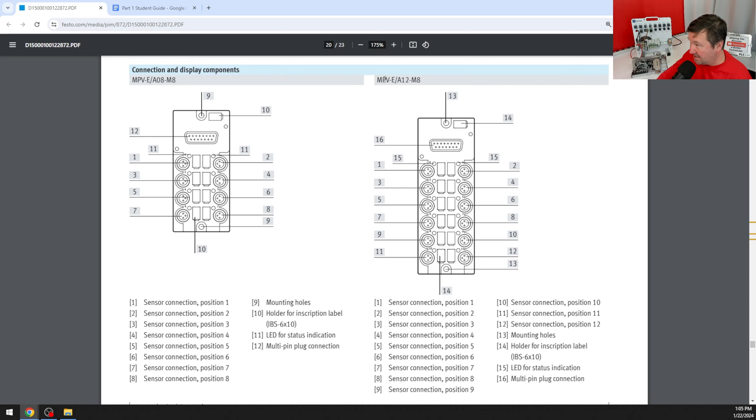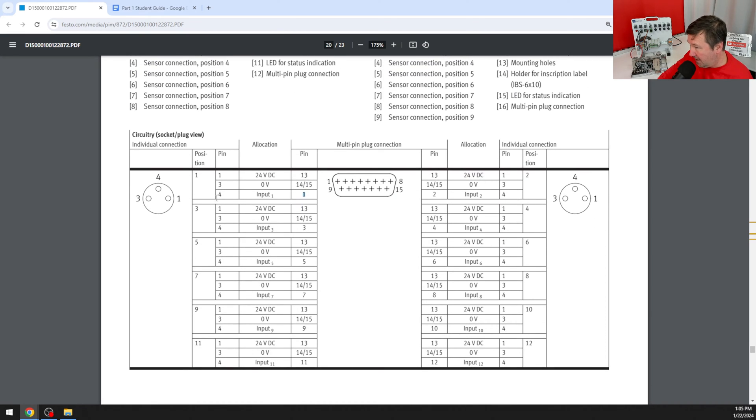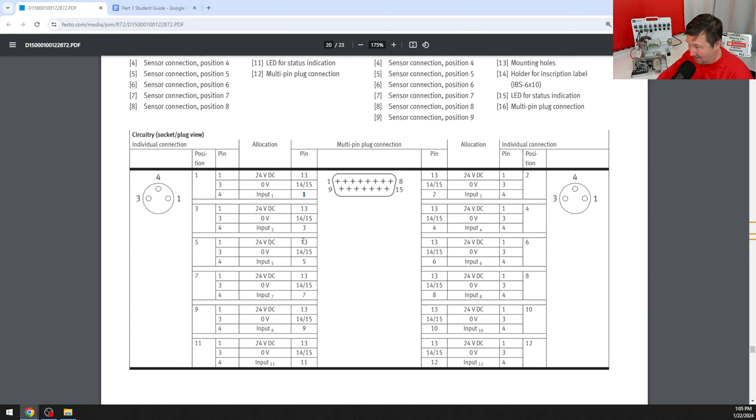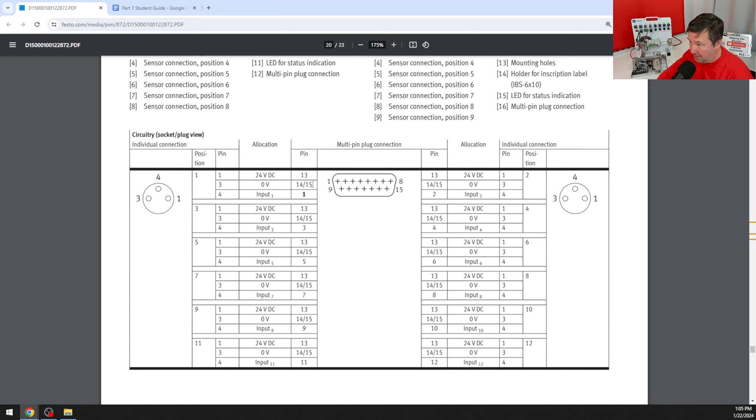Next let's look at the details of the MPV-E slash A12-M8. That's this right here and if we scroll down a little bit here are our pinouts. Notice plus 24 volt is pin 13 here, plus 24 volt is also pin 13 here and all the way through. So if we put plus 24 volt on pin 13 that's going to put power on all the pin 1s of that module. Same with our 0 volt. It's on 14 or 15 so just choose one of them and that will put 0 volt on pin 3 of all our modules and that will leave us pin 4 to work with.